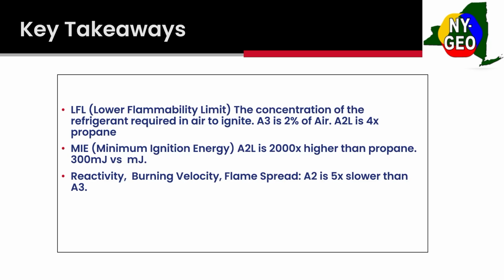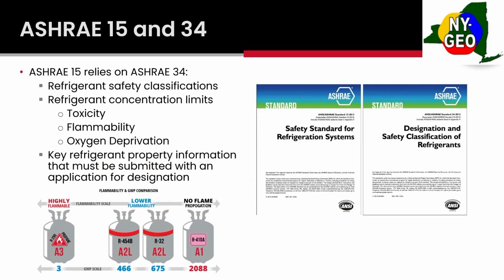So, all right, we're going to get into a couple of ASHRAE 15 and ASHRAE 34. Where the A2L and A3 comes from, it comes from ASHRAE 34. ASHRAE 34 defines the refrigerant concentration limits through toxicity, flammability, and oxygen deprivation. And you can see on the bottom here kind of the difference. So A1, no flame, A2L, lower flame, and then A3 is at the top. So this all comes from ASHRAE 34.